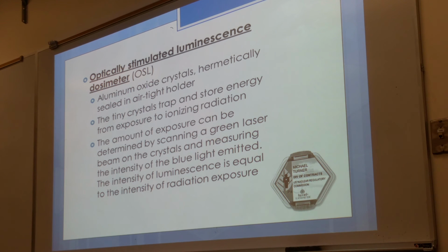OSL, or the optically stimulated luminescence dosimeter. I think that's what you guys have, right? The OSLs. Okay. Now, within the hermetically sealed casing is aluminum oxide. Same thing. The tiny crystals trap and store energy from exposure to ionizing X-rays. And then the amount of exposure can be determined by scanning a green laser beam on the crystals and measuring the intensity of blue light that the crystals emit. So scanned by green light, the crystals emit a blue light, and the intensity of that blue light is proportional to the amount of radiation it received.